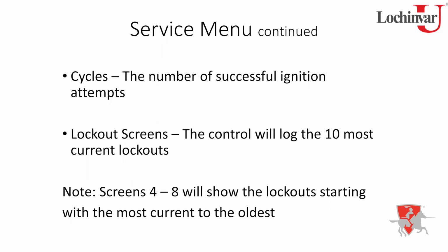Cycles, you see the number of successful ignition attempts, how many times it's actually lit off correctly and properly. And then lockout screens. The control will log the 10 most current faults. I won't say by date and time, because there's no date or time. Basically, it kicks the oldest one out when you get a new one coming in. Yeah, so screens 4 through 8, there's going to be 2 lockouts per screen, so that gives you the list you're looking for. So again, starting with the newest, going to the oldest.